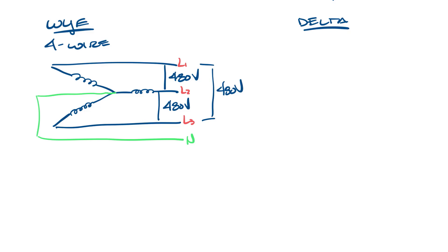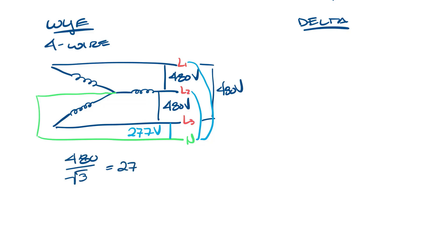But you can also get 277 volts from line to neutral. So from here to here, here and here, and here and here is 277 volts. The lower voltage is always the higher voltage divided by the square root of 3. So 480 divided by the square root of 3 is 277.